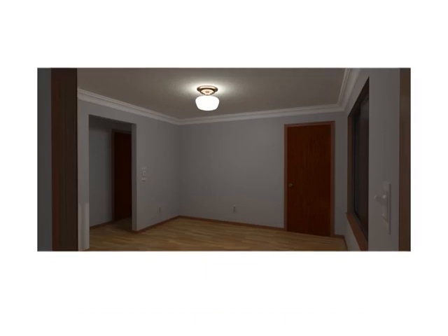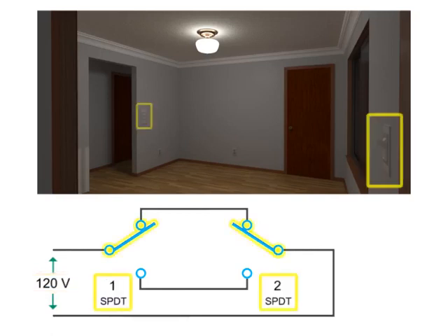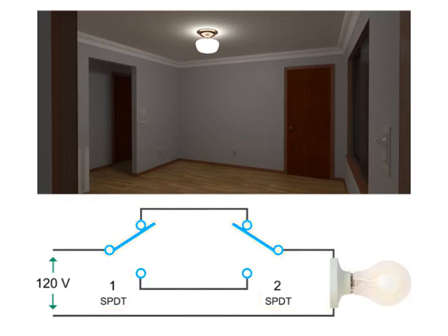switches in the room. In this diagram, depicting the operational components of a 3-way switch, we have a typical 120-volt source and two single-pole double-throw switches controlling a load, or in this case, a light bulb. This type of circuit has a black, red, and white wire handling the current.